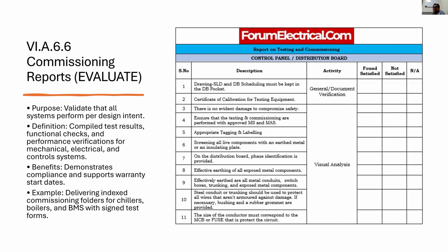So this is one example for the testing and commissioning of a control panel or distribution board. Mostly we have to check if this is really supplying power, if you turn it on and off, continuity, the insulation, what else, continuity and insulation test. Maybe there's a leak, so we have to ensure that all these testing instruments are calibrated. It is also very important.